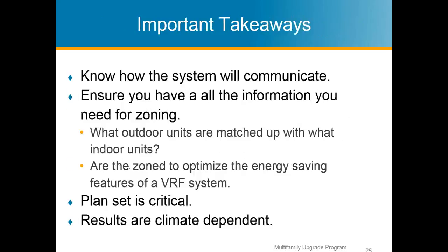So, a couple important takeaways for this webinar. Know your systems. Know how they communicate. Know if you're dealing with a 2-pipe or a 3-pipe, know where thermostats are going, and know how they're going to talk to each other. Know your selector boxes. Know the zoning. Those are all very important things. Make sure you have all the information you need. How many indoor units do you have? Which ones are matched up to the outdoor units? A plan set is critical to get because you want to really see where everything is getting served, right?